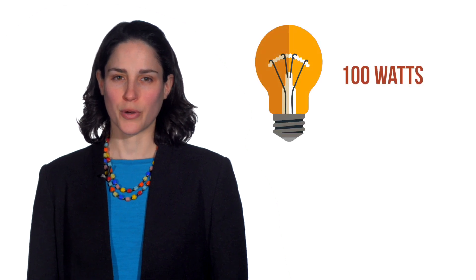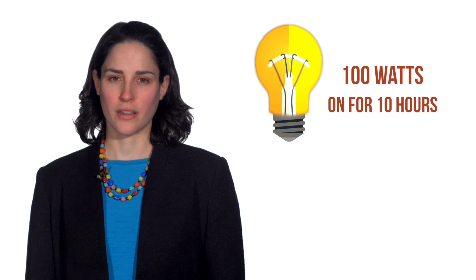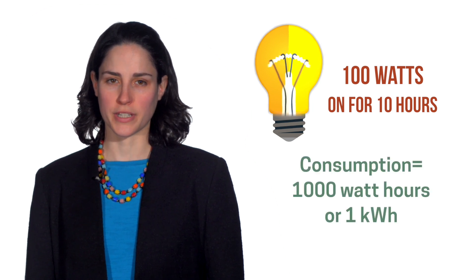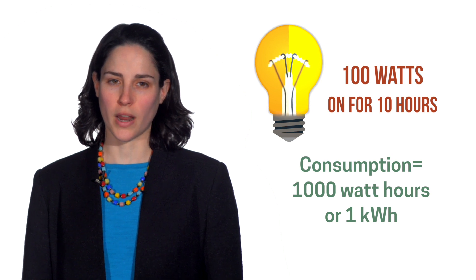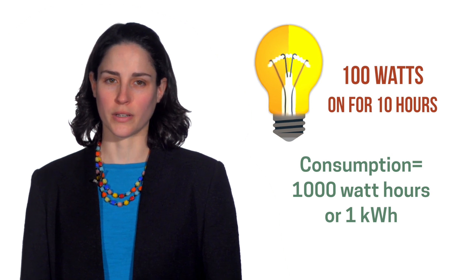Consider a single 100-watt light bulb. Suppose we turned this bulb on and kept it on for 10 continuous hours. That's 100 watts consumed for 10 hours. Our consumption in this case would be 1,000 watt hours or 1 kilowatt hour. When this single 100-watt light bulb is turned on, it will demand 100 watts or 0.1 kilowatts of power from the utility in order to function. No matter how long the light bulb is turned on, the bulb's demand remains constant.